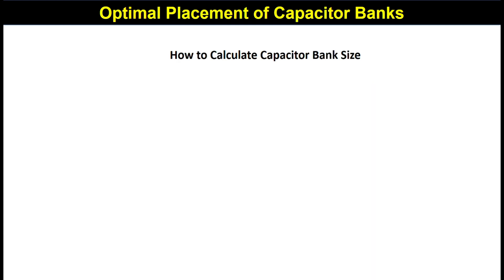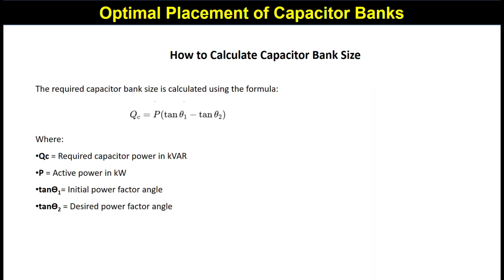How to calculate capacitor bank size. The required capacitor bank size is calculated using the formula: QC (the rating of the capacitor bank) = P (the active power) × (tan θ1 − tan θ2), where θ1 is the initial power factor angle and θ2 is the target power factor angle.